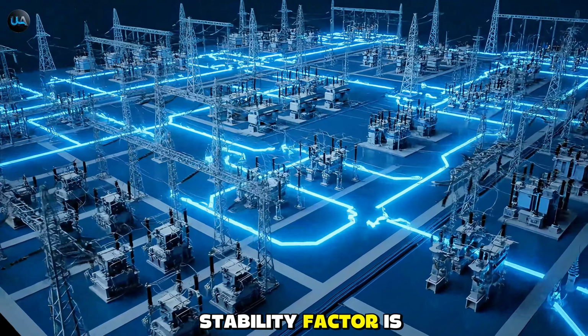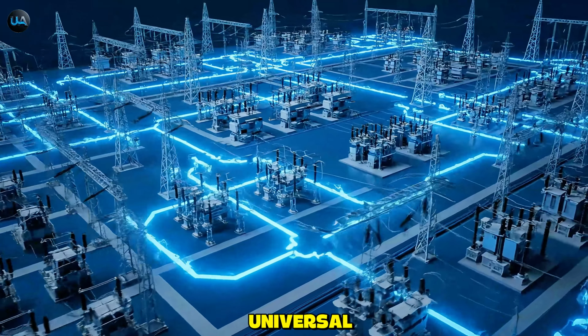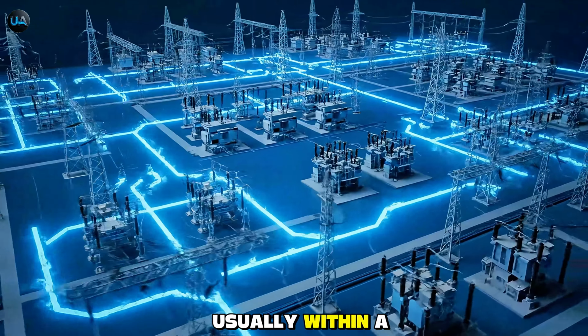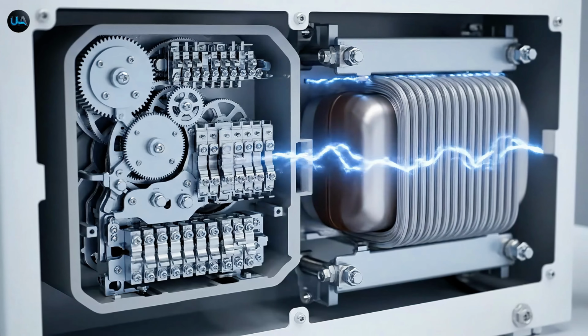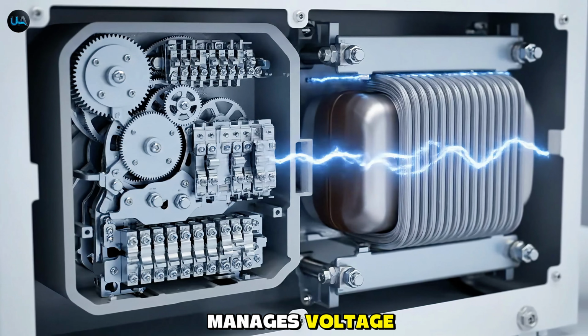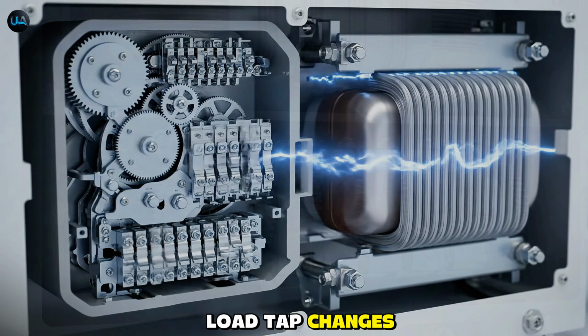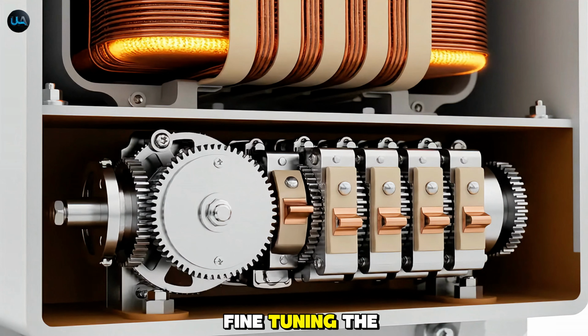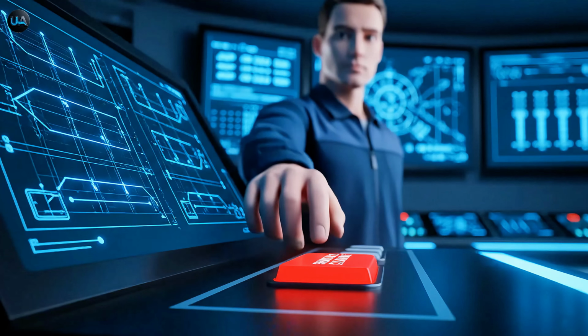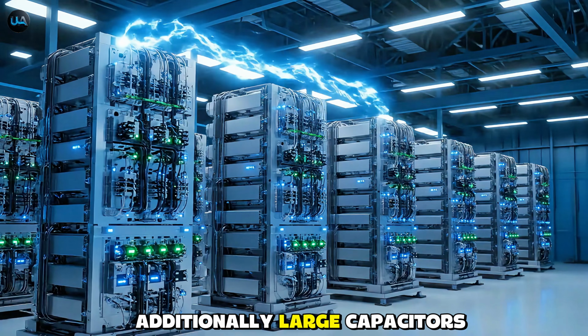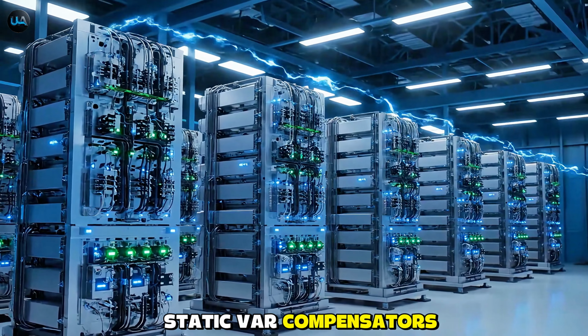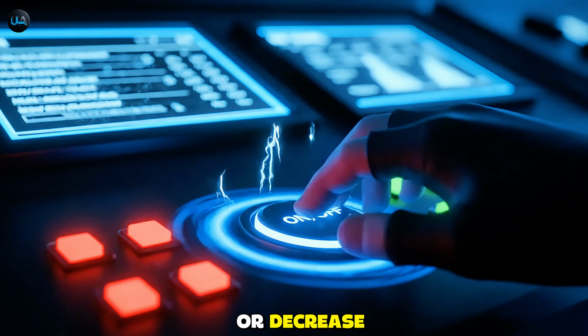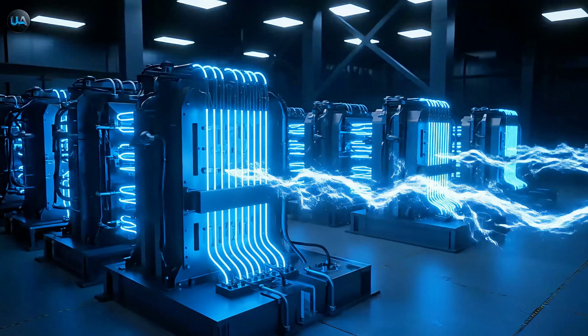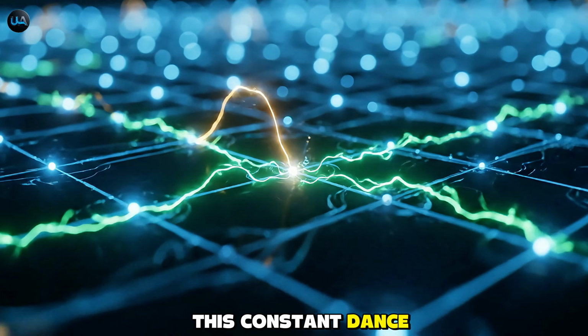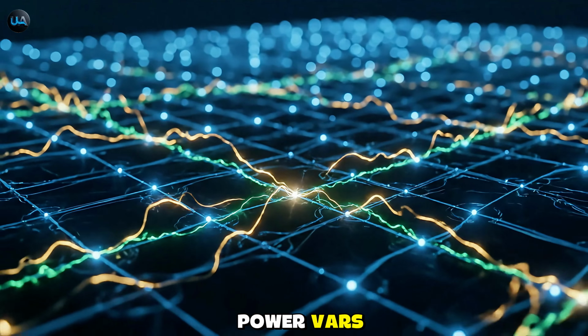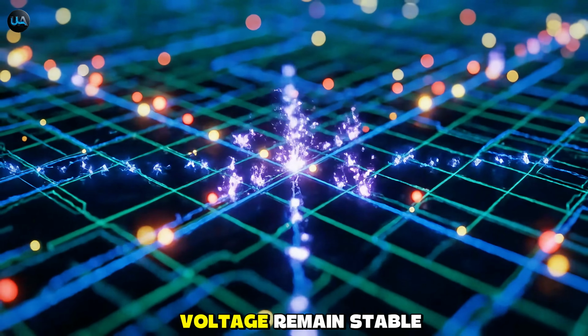The second major stability factor is voltage. While frequency is universal, voltage must be maintained locally, usually within a 5% tolerance. Reactive power (VARs) manages voltage. Transformers use on-load tap changers (OLTC) to adjust the turns ratio, fine-tuning the voltage output. Additionally, large capacitors and reactors, static VAR compensators, are switched in and out of the line to either increase or decrease local reactive power. This constant dance between active power (watts) and reactive power (VARs) ensures both the frequency and the local voltage remain stable.